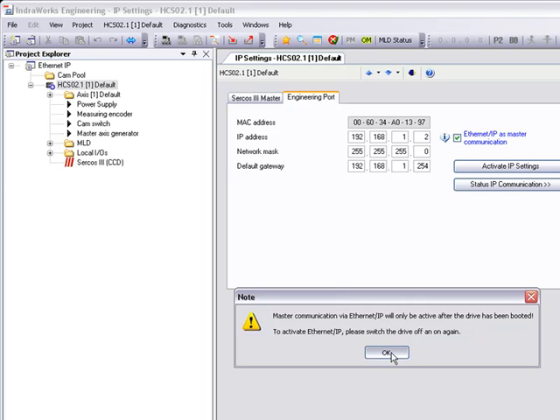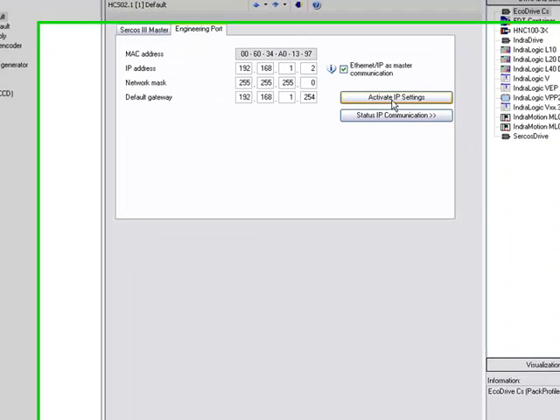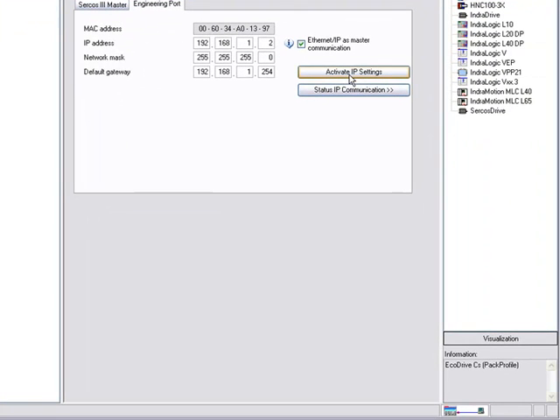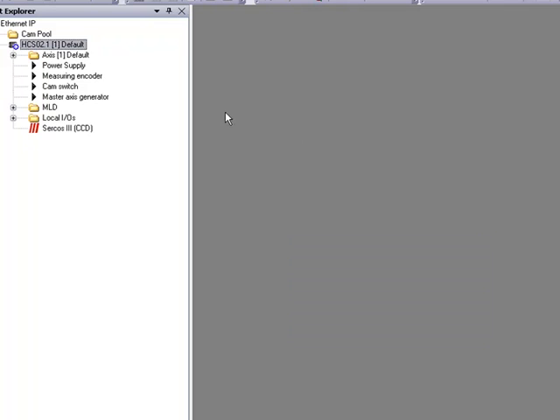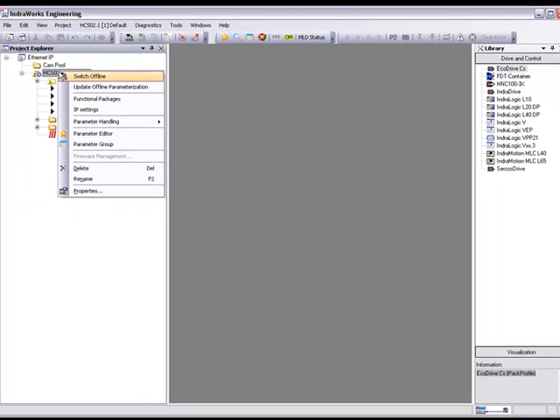We'll check the box and allow the Ethernet IP as our master communication and activate those settings. Once the box is checked to activate our Ethernet IP as our master communication, the drive power will need to be recycled for the drive to read that change.